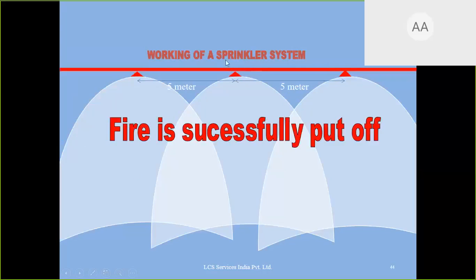Next is the sprinkler system. A sprinkler is an automatic water sprinkler. It has a pitch of 5 meter, and this sprinkler gives the water spray in this shape. This distance from here to here is 3 meter, and this is the overlapping period. Next, at 5 meter is a second sprinkler, and this is a third, and so on, so that no area is left without water in case there is a fire.